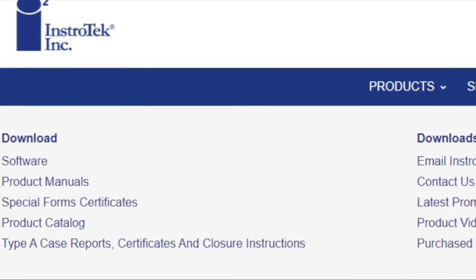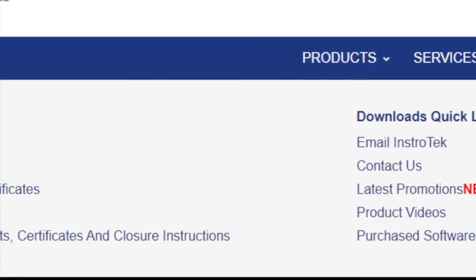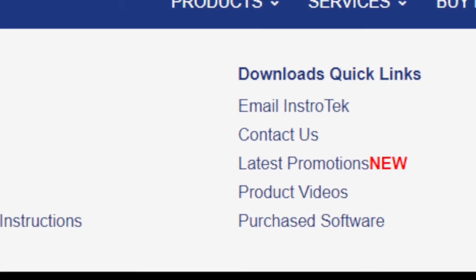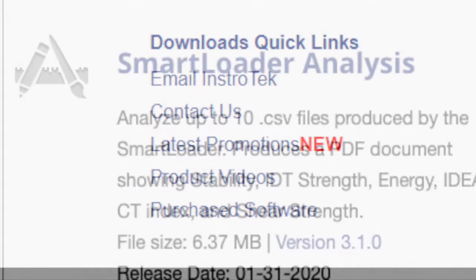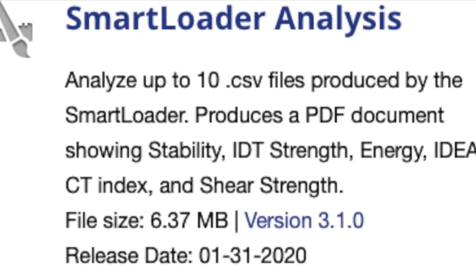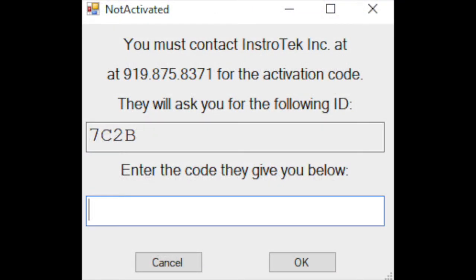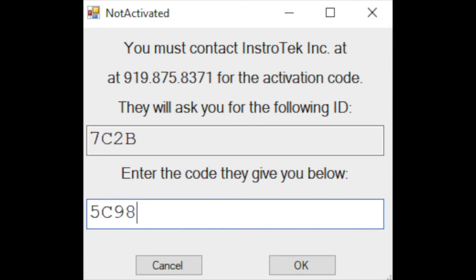To review your Ideal CT data collected with the Smart Loader, you'll need to download the Smart Loader analysis software from the InstroTek website. Visit www.instratech.com and choose purchased software from the downloads menu. Scroll down until you see the Smart Loader analysis box, then click on the version number to download. You will be given an ID number and prompted to call InstroTek for an installation code. Once the installation code is used, your Smart Loader analysis software will automatically open and you are ready to import your test data.